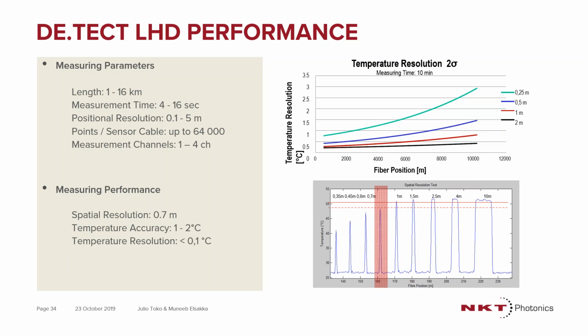In terms of resolution and temperature, we can achieve about 1 degree Celsius to 2 degrees, plus or minus 1 degree Celsius accuracy. And you can go down to a resolution of 0.1 degrees Celsius, depending on the length of your cable. As you can see in the graph on the top right, the further we move along the cable, the temperature resolution is also getting a little bit worse. But in the case of fire detection, for instance, we can push 16 kilometers without a problem. And that's where we have some limitation in terms of the standard rate of rise, how fast we can detect with the system.